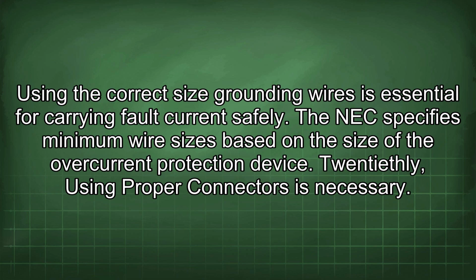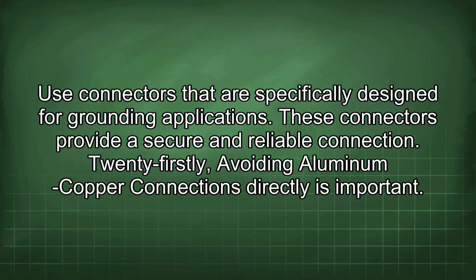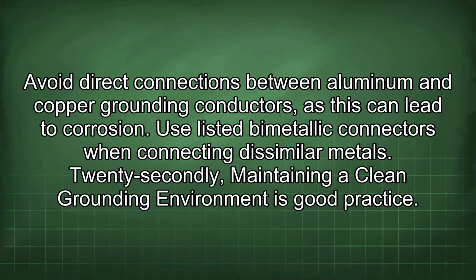Twentiethly, using proper connectors is necessary. Use connectors that are specifically designed for grounding applications. These connectors provide a secure and reliable connection. Twenty-firstly, avoiding aluminum-copper connections directly is important. Avoid direct connections between aluminum and copper grounding conductors, as this can lead to corrosion. Use listed bimetallic connectors when connecting dissimilar metals.